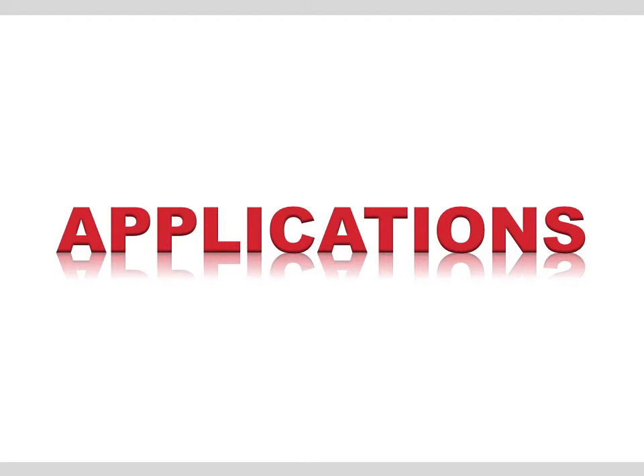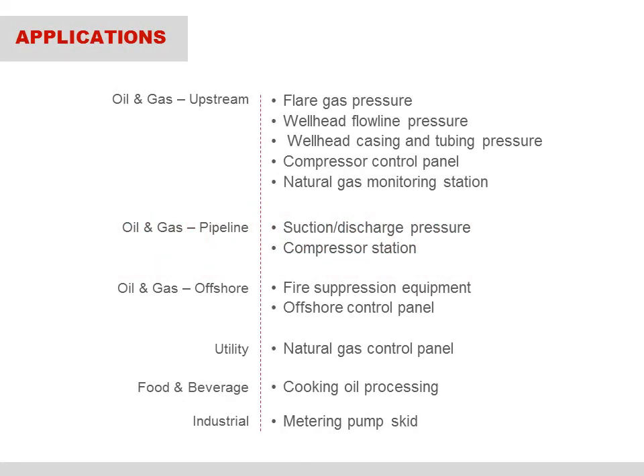Typically, Modbus RTU communications is only offered with full-featured process instruments. It is usually not offered in a compact, robust, and economical stick form factor transmitter like the 815 PT, which, by the way, is also HART capable. Let's take a closer look at specific applications.